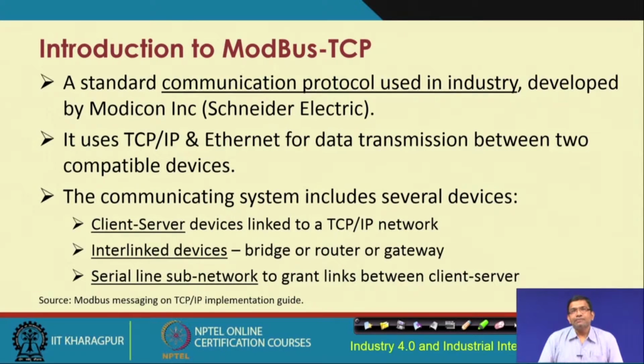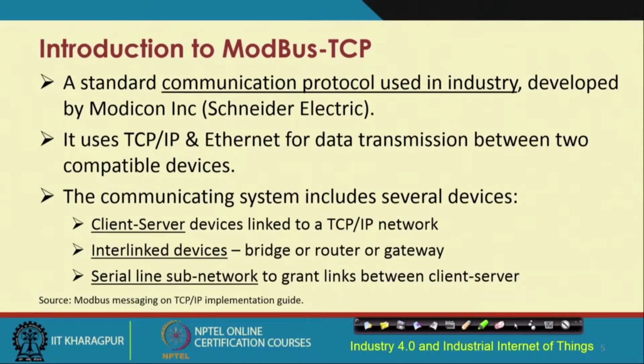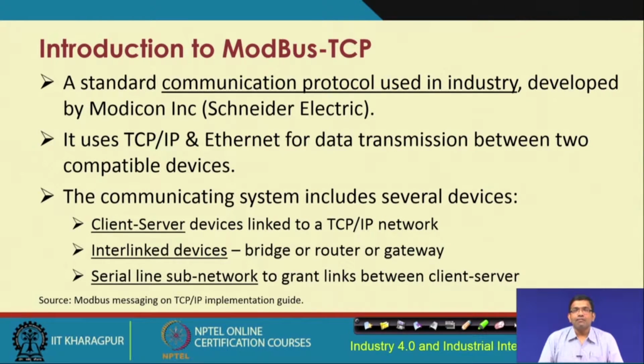Incidentally, Modbus TCP was proposed by present day Schneider Electric, which was earlier known as Modicon Inc. This protocol was proposed to cater to certain industry specific requirements that Schneider Electric or Modicon had in their plants, particularly requirements such as reliable communication, low latency communication, etc. This kind of protocol was required because the existing TCP IP protocol in its standard form was not very suitable. So, it had to be modified in order to be used for the industrial communication requirements in manufacturing plants. Schneider Electric came up with their own protocol, which later became an industry standard communication protocol, and Modbus TCP is a popularly used protocol at present.